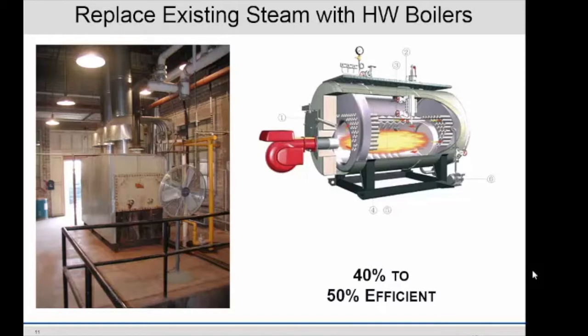Steam boiler, this is an actual project I did, but it's just a small steam boiler. The steam boilers we work with, like at Tinker Air Force Base, are huge. They're as big as this part of the conference center. This one just shows you how they operate. They're just so inefficient. They're just fire, making steam and heating everything up, and you're lucky if you get 40 to 50% efficiency out of them. Get rid of them.